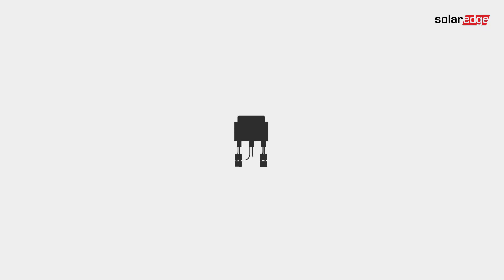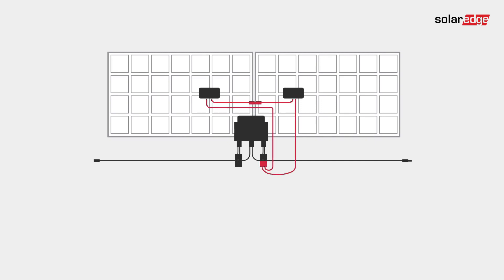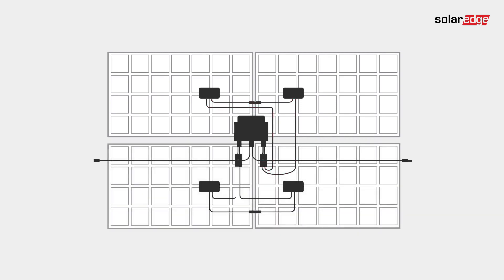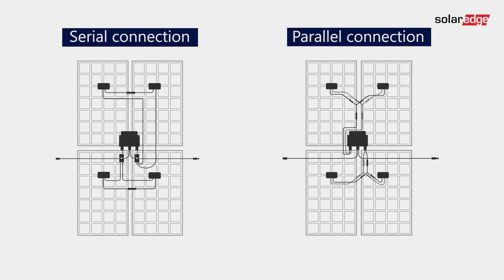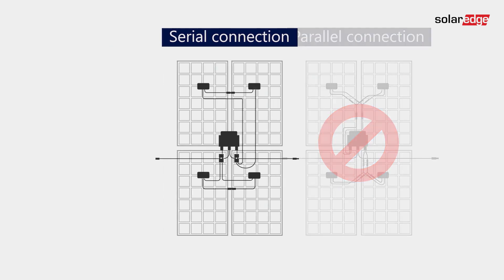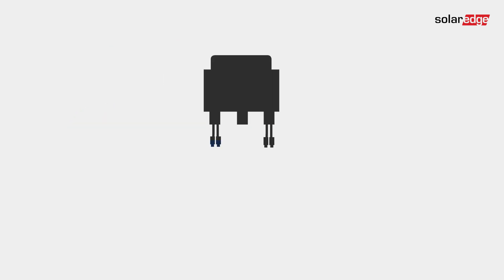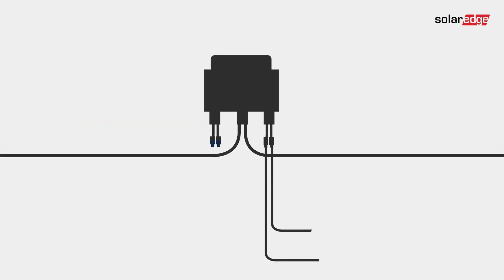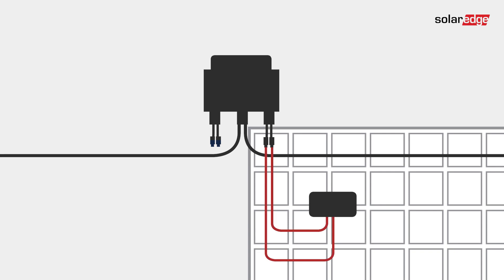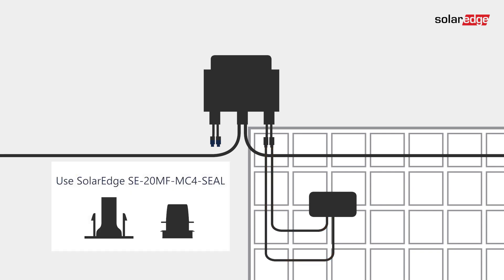The M1600 only supports serial connections of two 72-cell modules to each input. Parallel connections are not supported. Ensure that one module is always connected to the primary input at all times and do not leave any input unprotected.